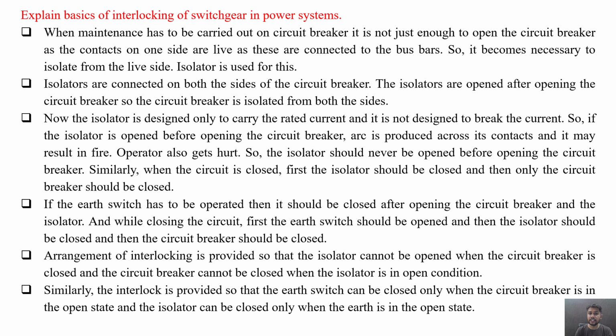Similarly, when the circuit is closed, first the isolator should be closed and only then the circuit breaker should be closed. Otherwise, the circuit breaker is disconnected or isolated from both the sides. It is not connected with the bus bars.